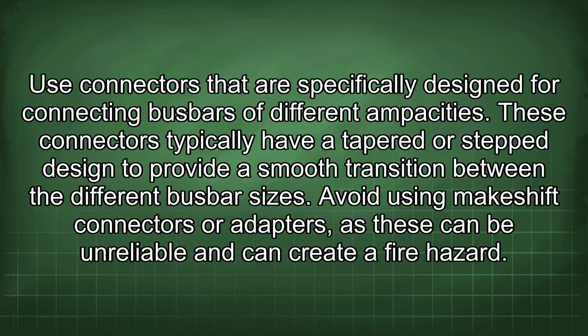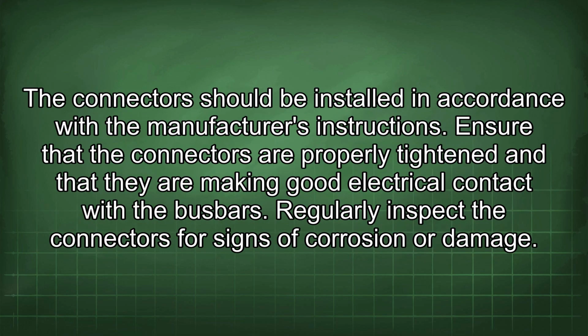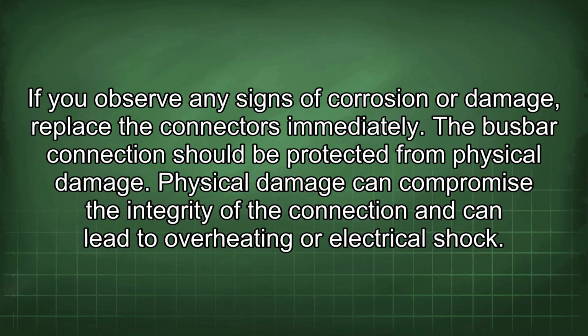Avoid using makeshift connectors or adapters, as these can be unreliable and can create a fire hazard. The connectors should be installed in accordance with the manufacturer's instructions. Ensure that the connectors are properly tightened and that they are making good electrical contact with the bus bars. Regularly inspect the connectors for signs of corrosion or damage. If you observe any signs of corrosion or damage, replace the connectors immediately.